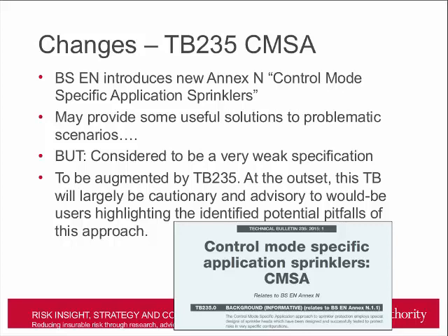It's largely cautionary and advisory, highlighting some of the potential pitfalls of the approach to users. For example, the CMSA approach is very dependent on the type of head you would use and the approval limitations on that head, and the BSEN doesn't and can't deal with that, but nevertheless that's an important design issue that must be considered in the round.